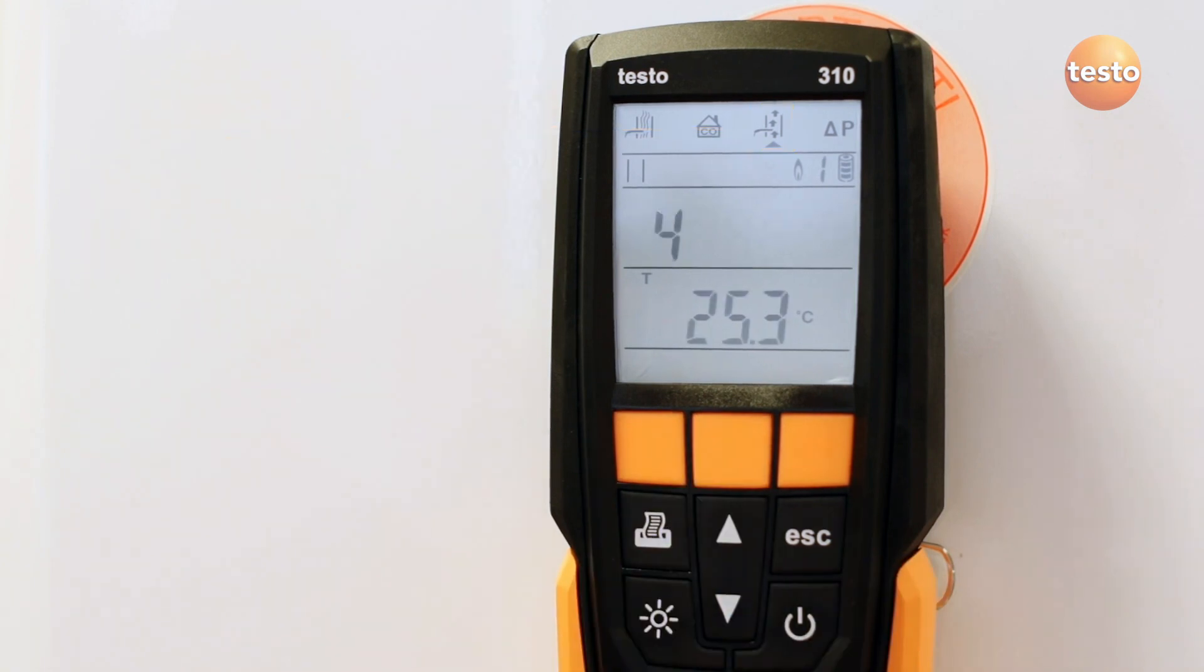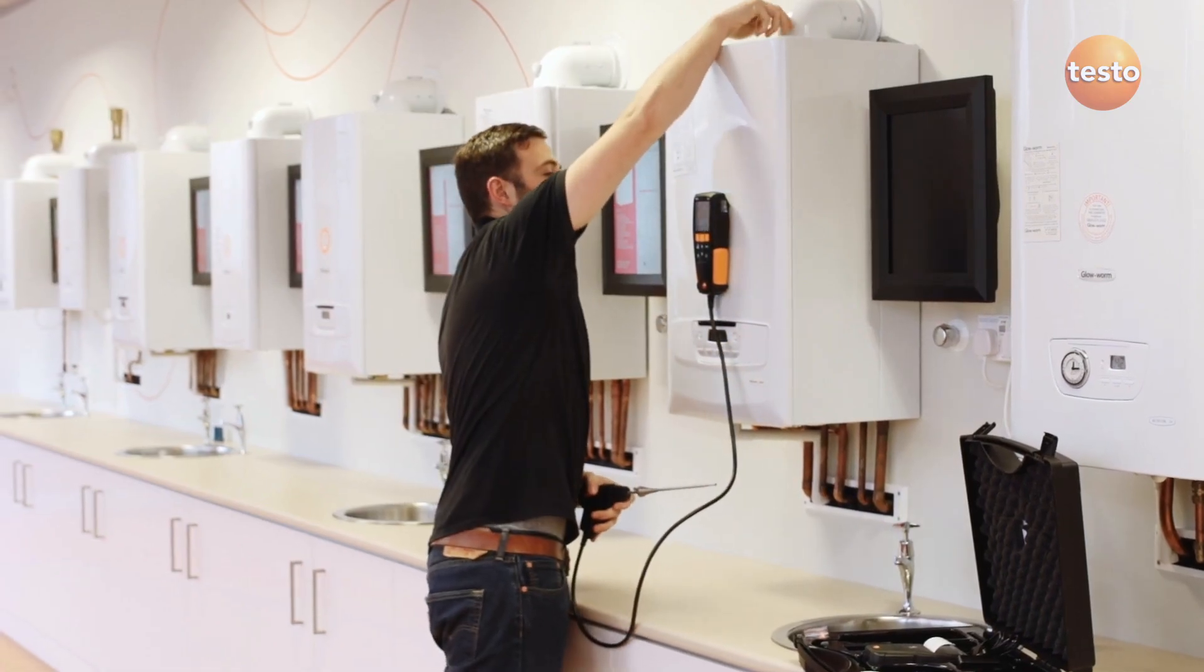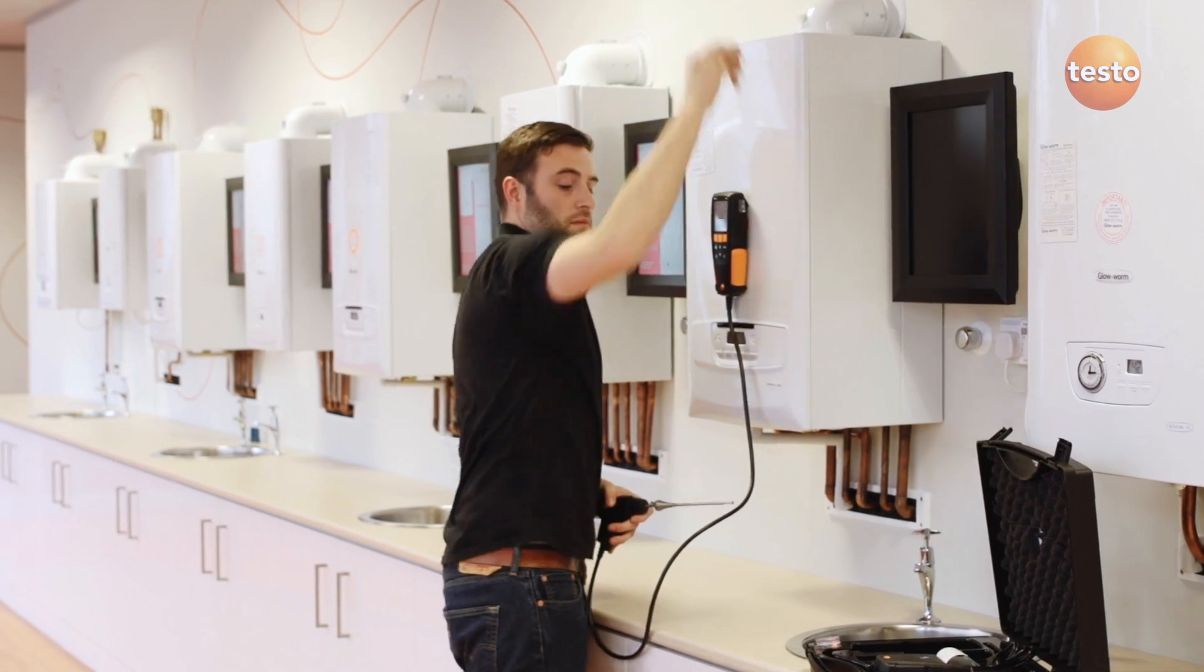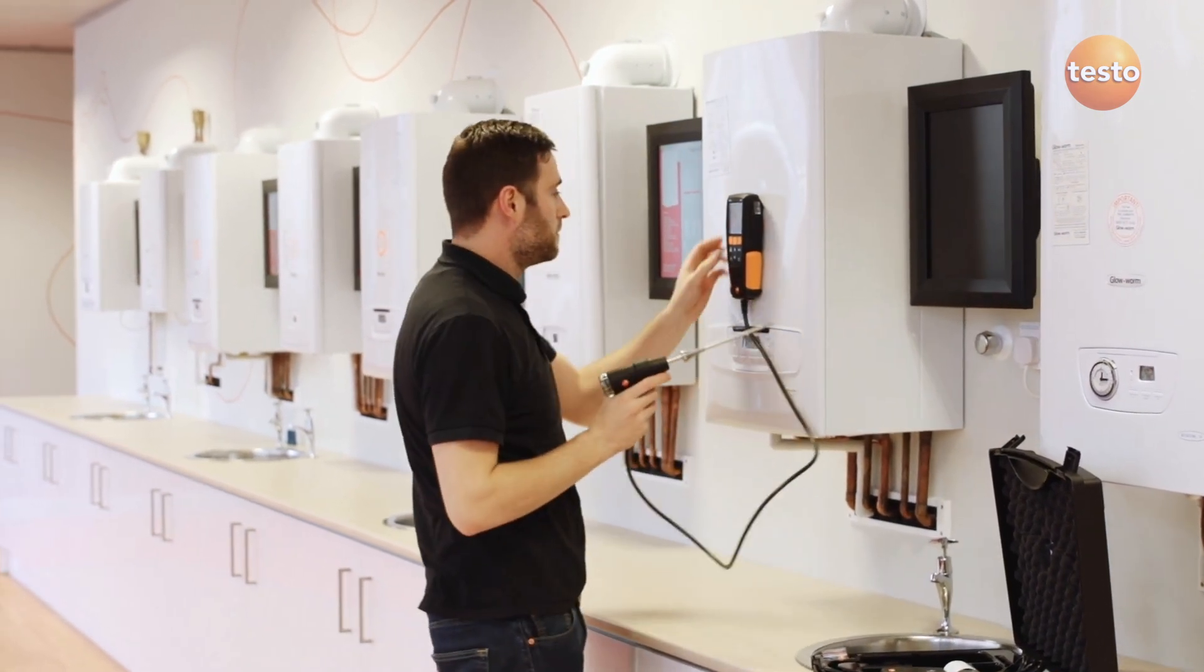Press start. The pressure sensors adjust to the barometric pressure for five seconds. It's important that the probe is in fresh air while the pressure sensors are zeroed. Then it's ready for the probe to be put in the flue with the boiler running.